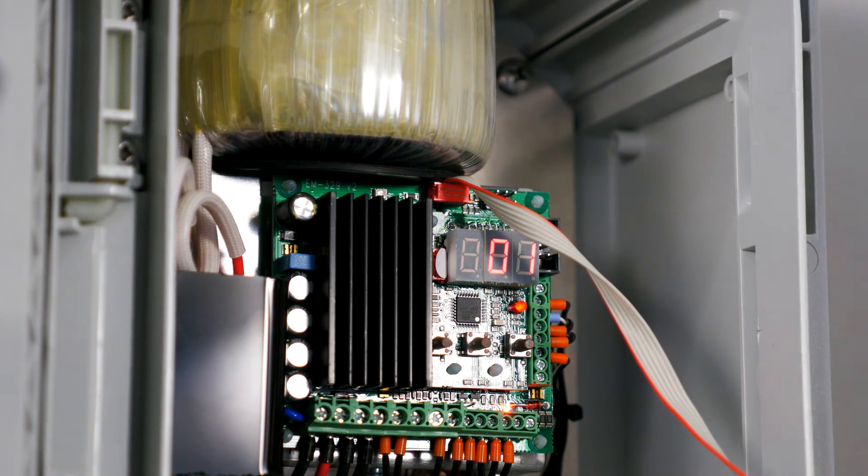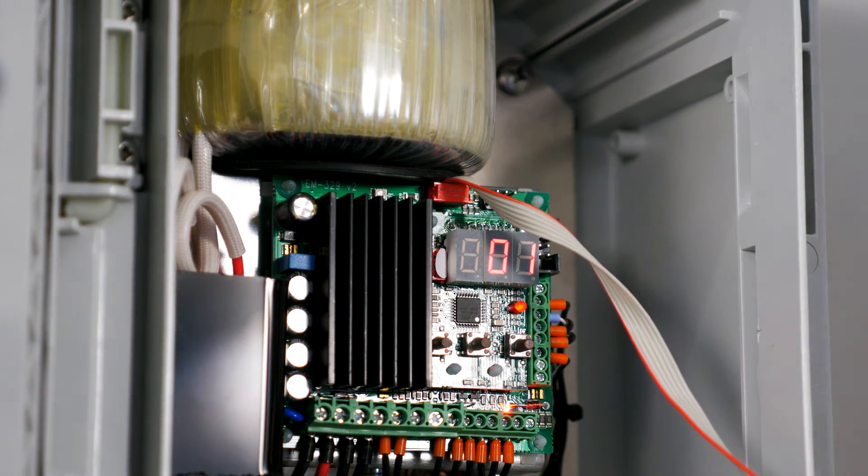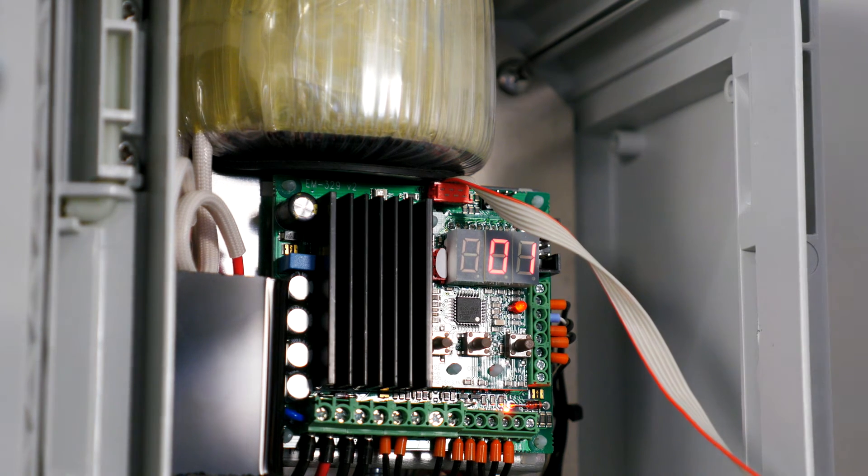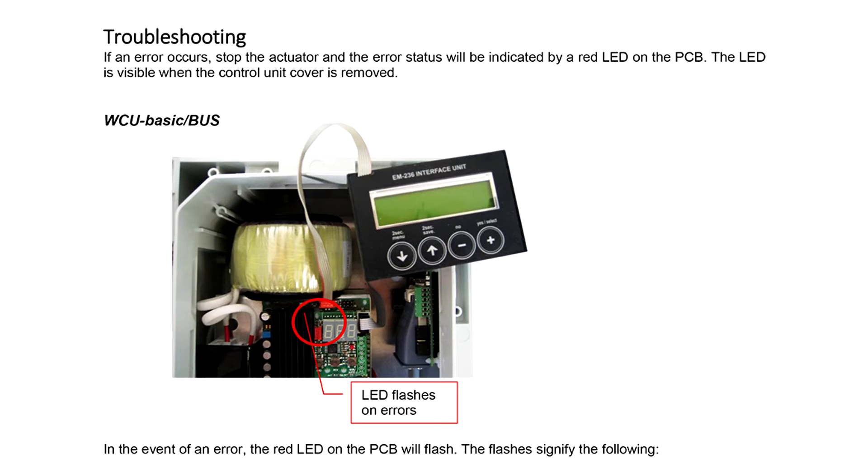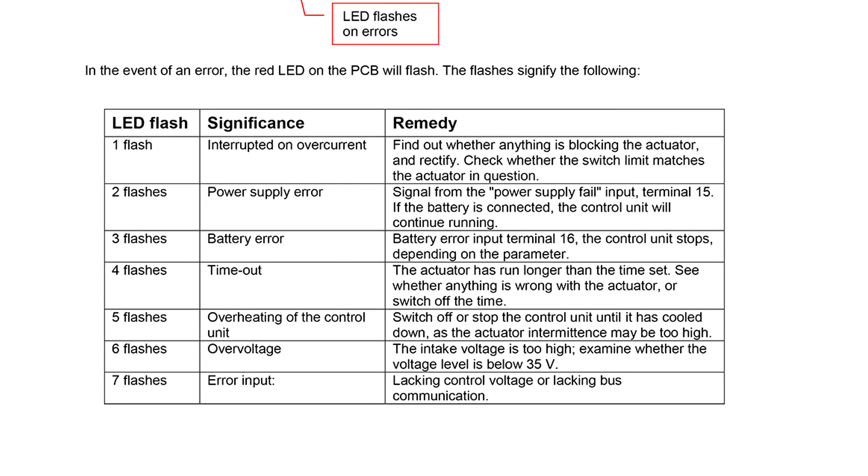If this troubleshooting does not solve the problem, you must check how many times the red LED on the PCB flashes. On this overview, you can see what the different number of flashes means. Follow the corrective action as appropriate for the number of flashes you see on your LED.